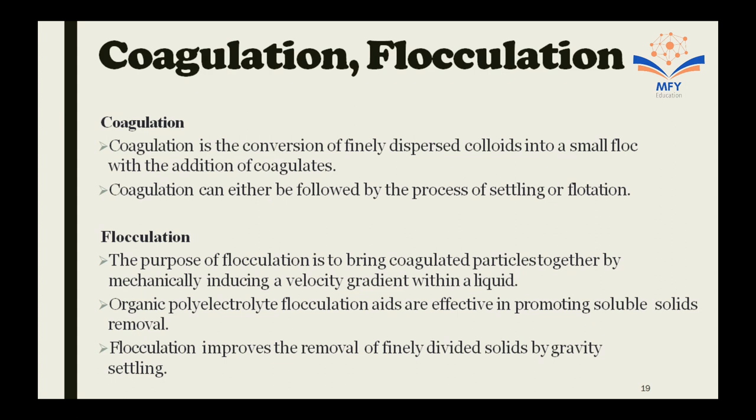Coagulation and flocculation. What are coagulation and flocculation? Coagulation is the conversion of finely dispersed colloid into small flocs with the addition of coagulants. Coagulation can be followed by the process of settling or flotation. Flocculation: the purpose of flocculation is to bring coagulated particles together by mechanically inducing a velocity gradient within a liquid. Organic polyelectrolyte flocculation aids are effective in promoting soluble solid removal. Flocculation improves the removal of finely divided solids by gravity and settling.